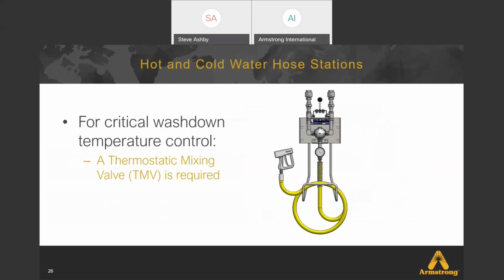For critical washdown temperatures, then you have to add a thermostatic mixing valve. In these scenarios, typically the water is generated 5 to 10 degrees higher than what the desired washdown temperature is, and then we can blend that with cooler water, and then we can give it very precise temperature for the washdown if that's a critical need.